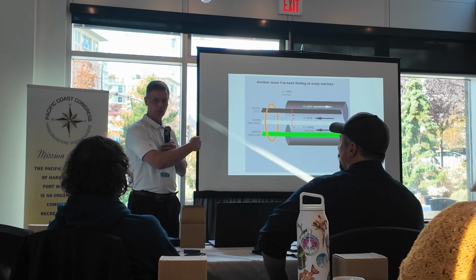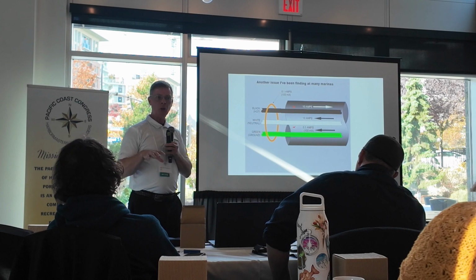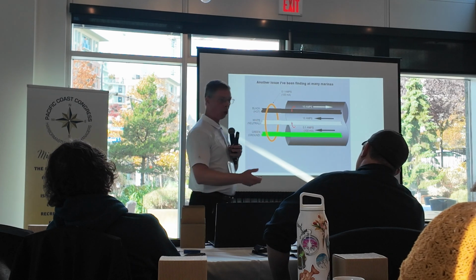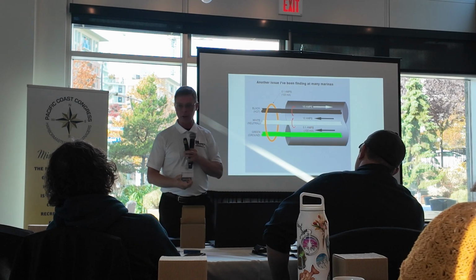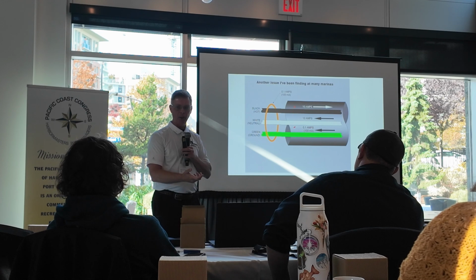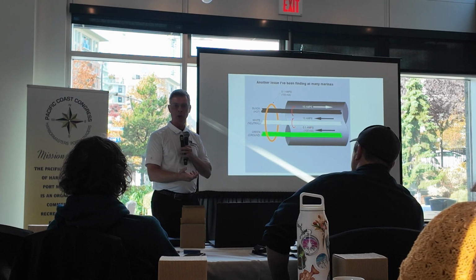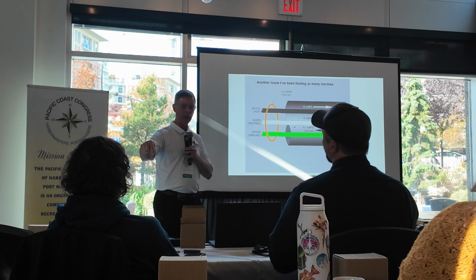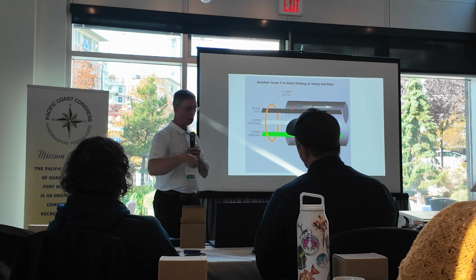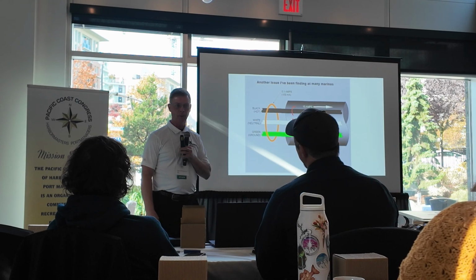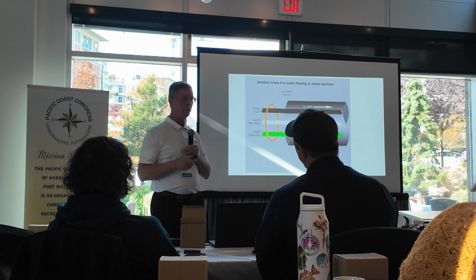on his boat. So if I start measuring leakage currents just by clamping cords, and I measure 3 or 4 boats that have leakage current on them, then you have to isolate which boat it really is. Because there is a bad boat somewhere that's leaking current that's transmitting to other boats and getting on the grounding system. So that's a very important thing to understand.